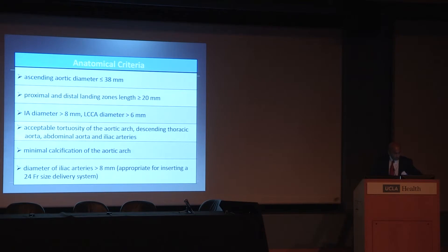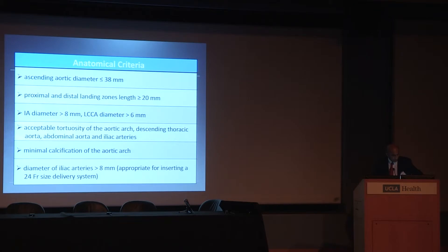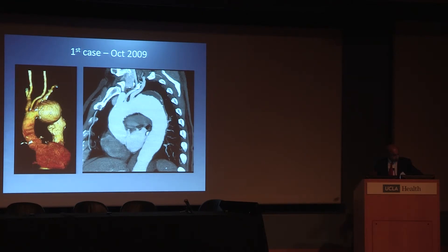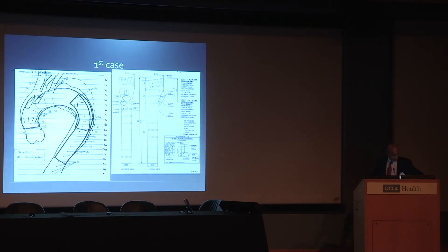Cook has done a good job of keeping within inclusion criteria: the ascending aortic diameter must be less than 38 millimeters, otherwise you may not be dealing with a normal ascending aorta, which could lead to mid- to long-term problems. The proximal and distal landing zones requirement of 20 millimeters is being pretty chintzy — you really need more than that with these kinds of grafts, especially in the ascending aorta. Minimal calcification is preferred because stroke is really one of the Achilles heels of these procedures.